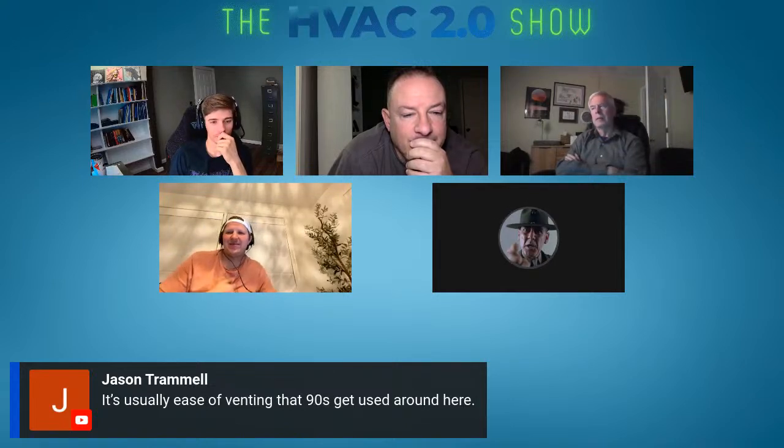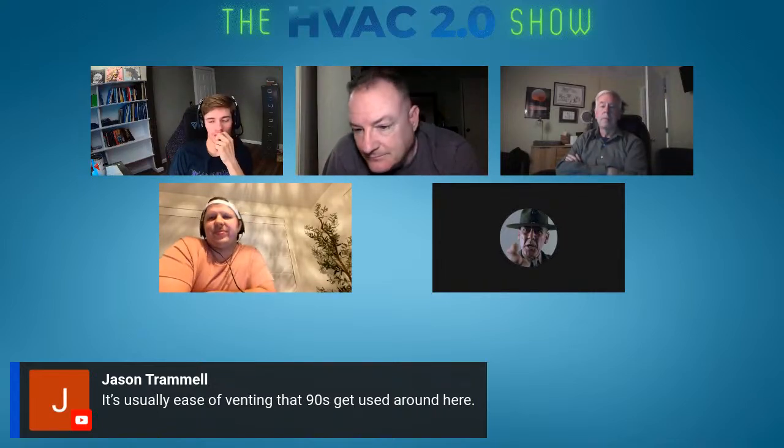Well, I've always been a lot more of a fan of using an 80% furnace for hybrids than high efficiency anyways, just because there's not much of a gain going from 80% to 98%. Rebate money, and this is the reason to go to a 90%er if you're doing a new house, or there's some kind of a major obstacle to doing the venting, or if you're using communicating equipment.